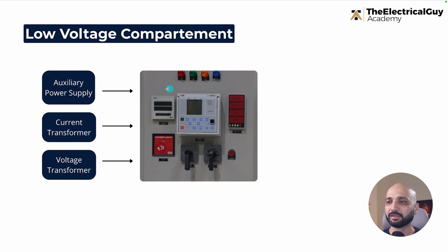That's the second source. The third source is the voltage transformer. Same as the current transformer case, we have voltmeters, and we have protection specific to voltage. All those things are fed by the voltage transformer. The voltage transformer will take, let's say, 36 kilovolt, step it down to 110 volt by root 3 or 220 volt by root 3, and then it will be fed to the relays and meters that we have here. So these are the three sources of supply for our low voltage compartment, and that's why CTs and PTs are used inside the switchgear panels, right?